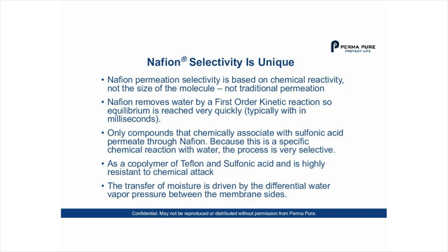Traditional permeation works like a bug screen — holes of a certain size match up with molecules you want to pass from one side to the other. That's not how Nafion works. With Nafion, water actually becomes part of the chemical structure, and as a result Nafion moves water by a first-order chemical reaction, reaching equilibrium very quickly. Only compounds that chemically associate with the sulfonic acid permeate through Nafion. Because this is a specific chemical reaction, the process is very selective — when humidifying with Nafion, truly only water passes through, not oxygen or other chemicals in solution.